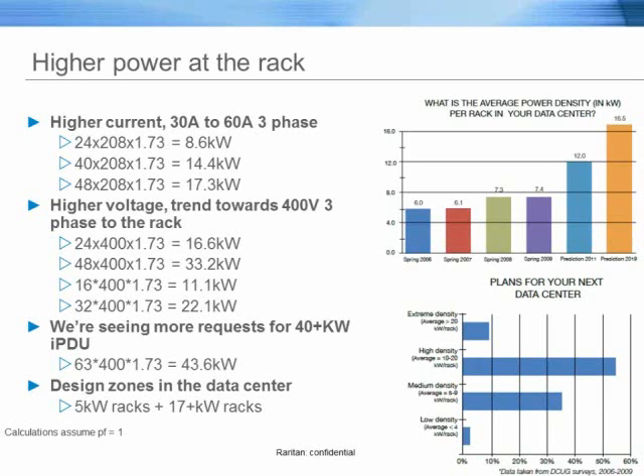We can bring in 7.3 kW, and these are all the derated values. That's of course a 60 amp PDU, a 50 amp PDU, and a 30 amp PDU. That's a lot of power: 8.6, 14.4, 17.3. When we start to factor in what we can bring in using 400 volt three-phase, now we're taking those numbers and we're doubling them. We used to show customers going from simple 208 into three-phase, giving you a huge advantage. Now we're taking that three-phase advantage, traditional three-phase, and we're bringing a 30 amp three-phase up to 400. And you can really bring in a huge amount of power to the rack.